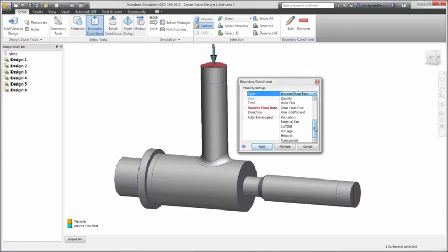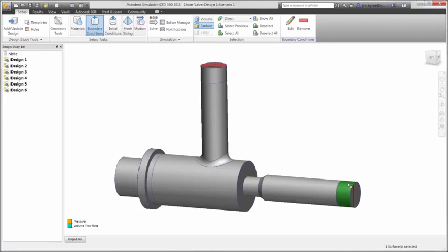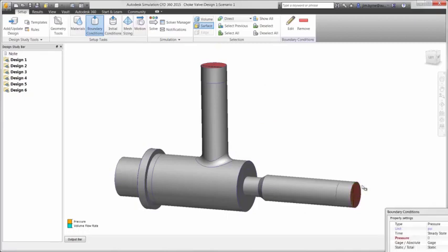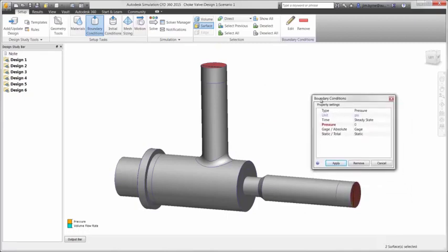This includes items such as volume flow rate, thermal characteristics, humidity, and even electrical current or voltage can be applied to simulate heat generation. In this case, we need a volume flow rate of 50 gallons per minute and a gauge pressure of 0 for the other end. That's enough information to gain the results we need for the velocity and pressure drop.